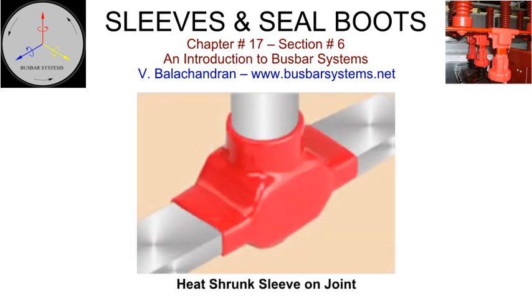One major problem associated with heat shrinking of sleeves is that it may not be free of voids, even when covering a straight flat or round conductor. It is very difficult to have a void-free sleeving on a bus bar that has a bent profile, since the sleeve shrinks to the least dimension. A shrunk sleeve is stressed on its surface. A minor flaw or a sharp corner on the surface of the conductor can develop into a major defect in sleeving during assembly. It is advisable to have sleeved conductors clamped, instead of bolted, to the support insulator to fully derive the additional safety provided by sleeves.